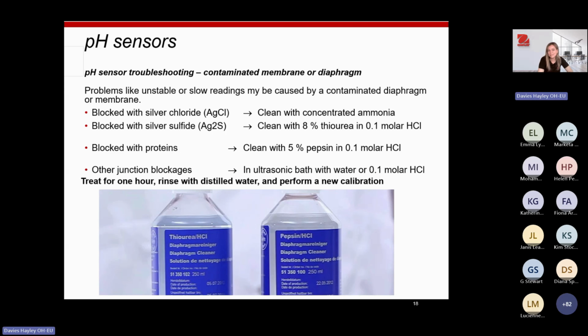So just a little bit of sensor troubleshooting then. If you're having any issues when you're trying to calibrate, then there could be something else wrong that could be rectified. You may have a contaminated membrane or diaphragm, and problems like this show unstable or slow readings. There are a couple of other options that you can go for, for a bit of maintenance.